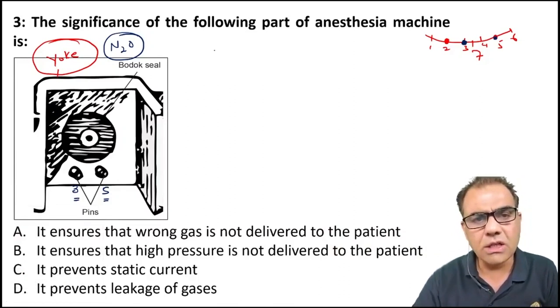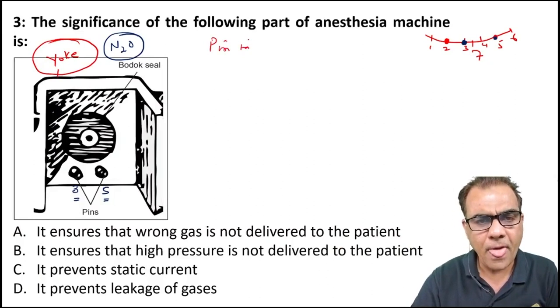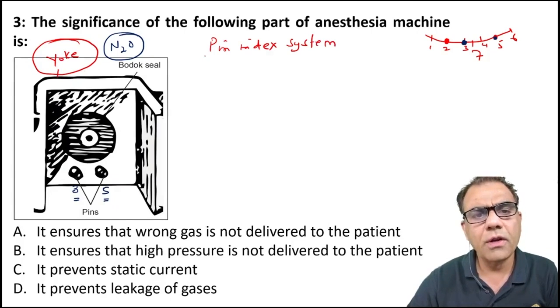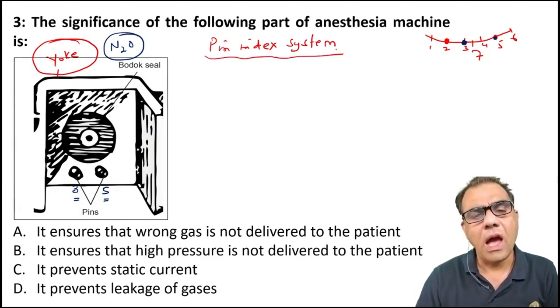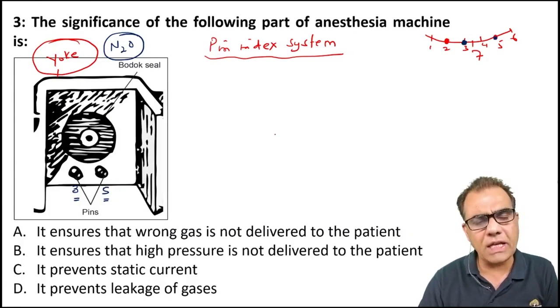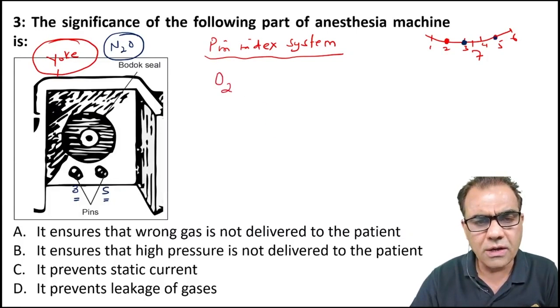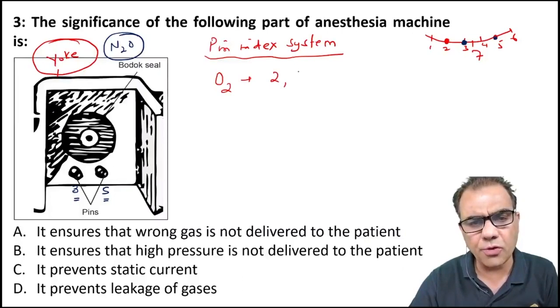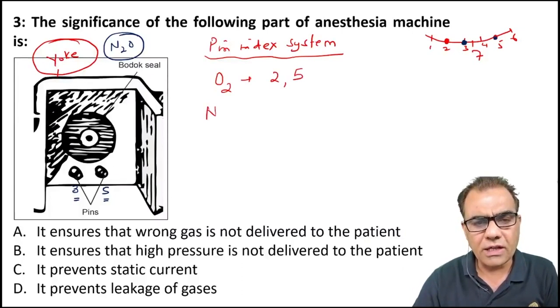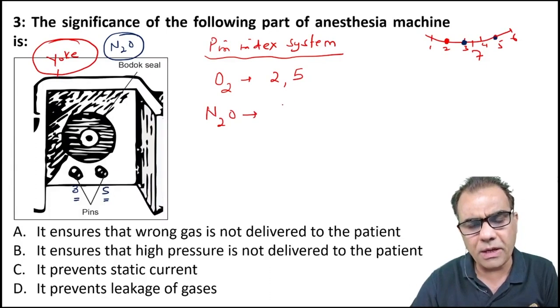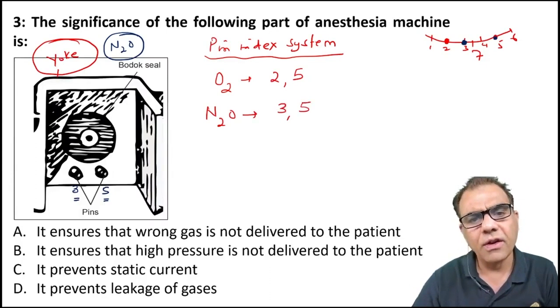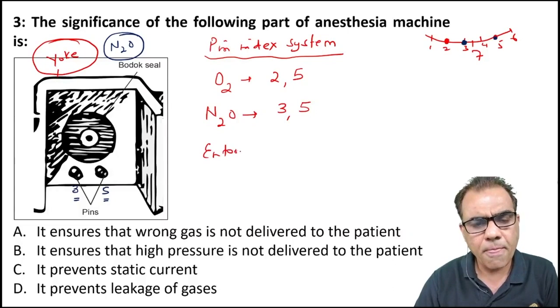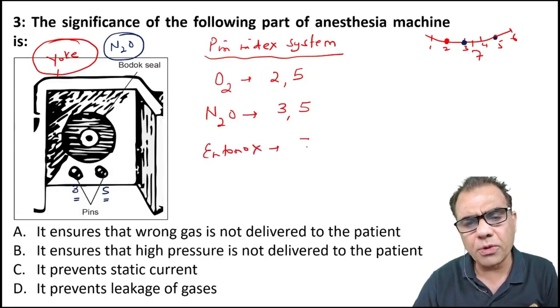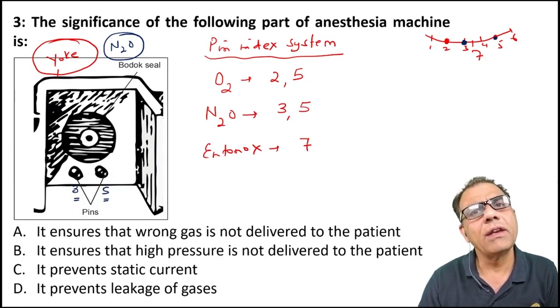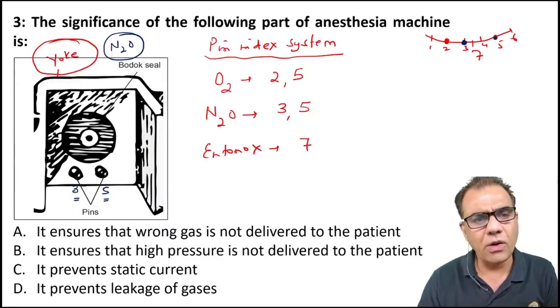So this is actually the pin index system, and the aim of the pin index system is to prevent the wrong fitting of cylinders. And you have to remember the pin index positions for different gases. Oxygen, the two pins are placed at positions 2 and 5. Nitrous oxide, the two pins are placed at positions 3 and 5. And Entonox has only a single pin at position 7. Fine. So now we can look at the question.